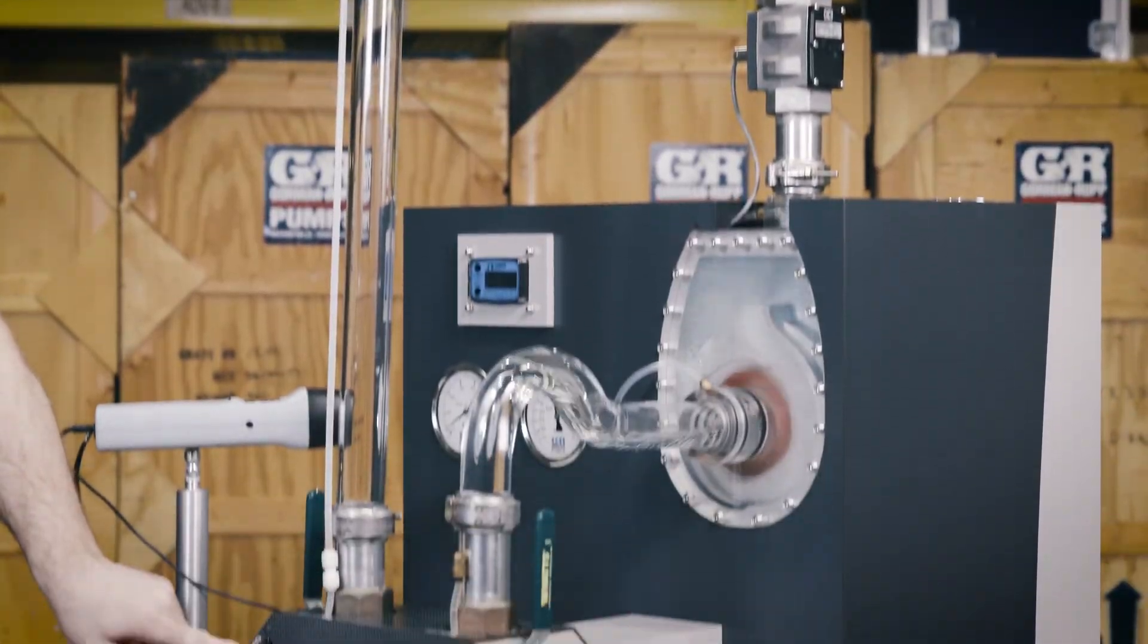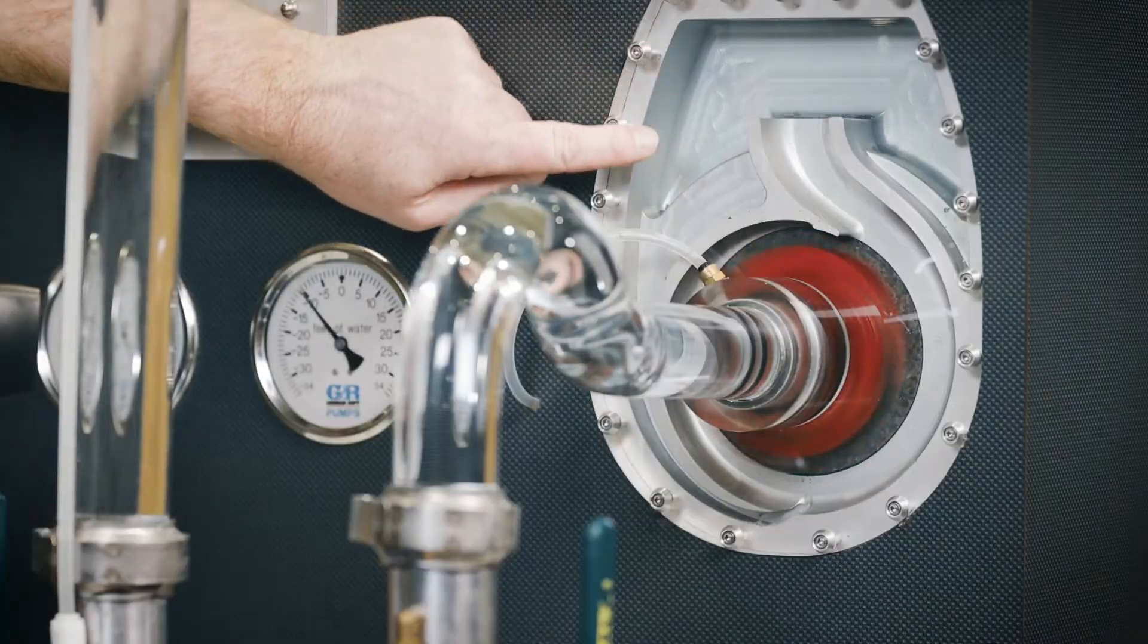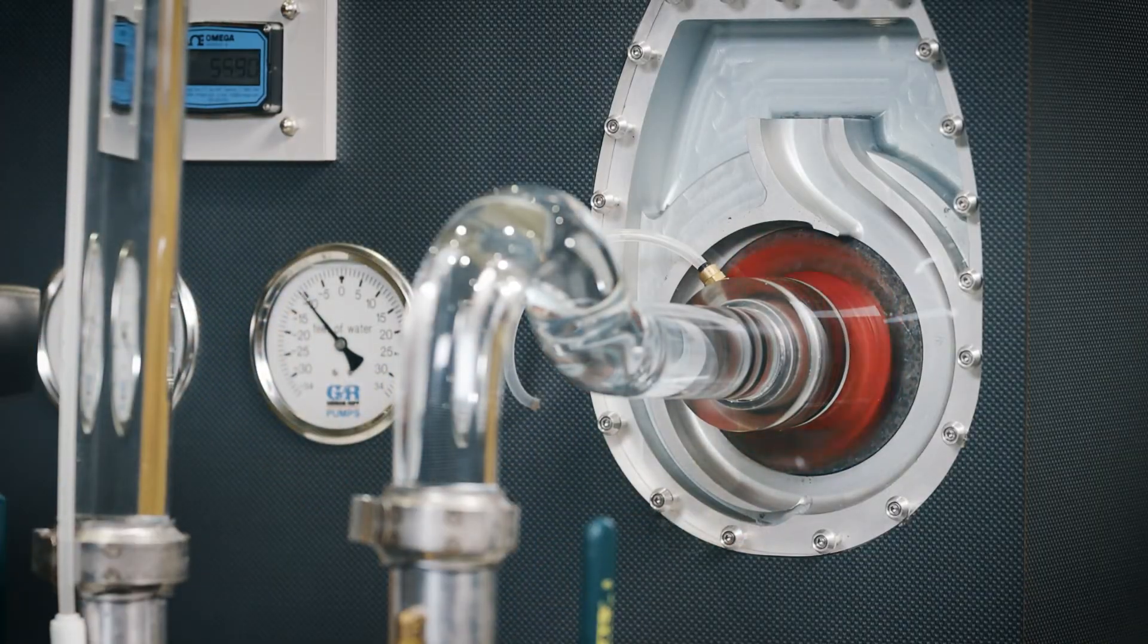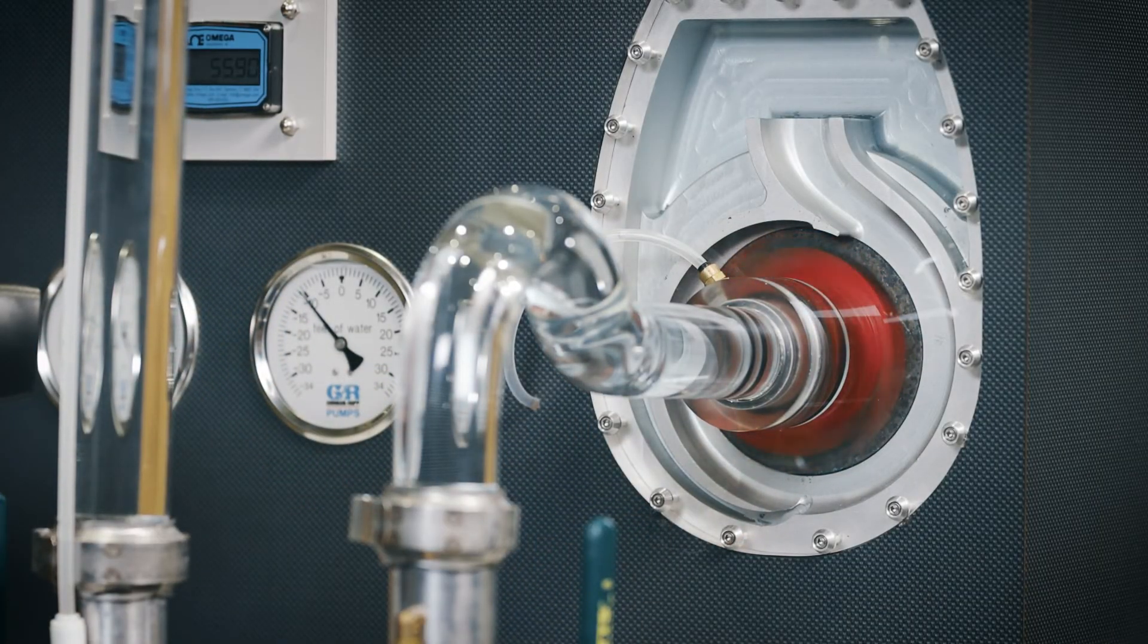The water within the pump casing is rerouted through a recirculation port back to the impeller, sustaining the hydrodynamic seal. This cycle continues until the pump is primed.